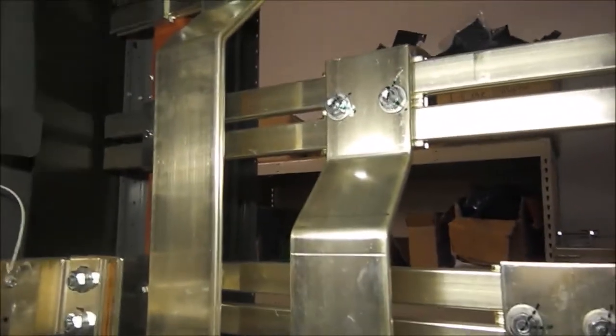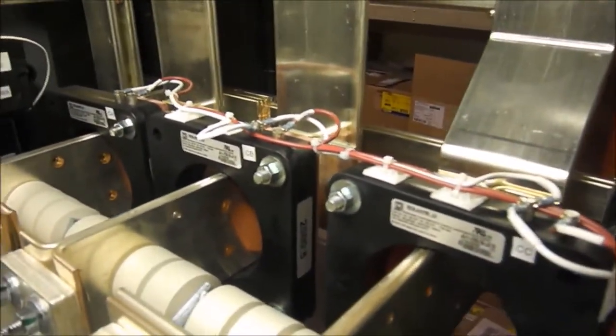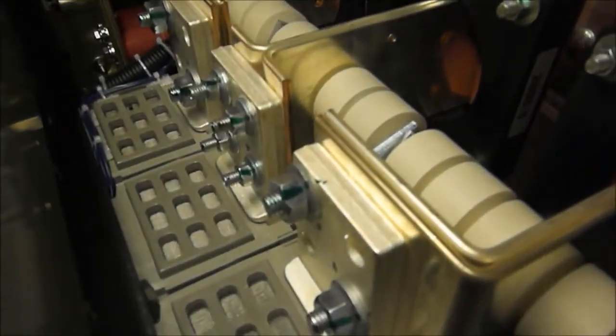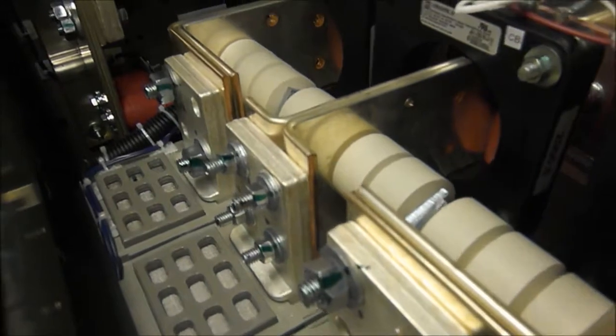When we look inside the switchboard we see three-phase power comes in over three main buses, travels down through three CTs or current transformers to measure the power and then continues on through three buses into the top lugs of the circuit breaker.